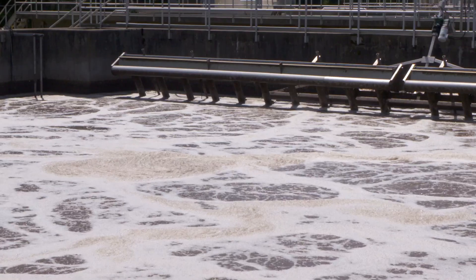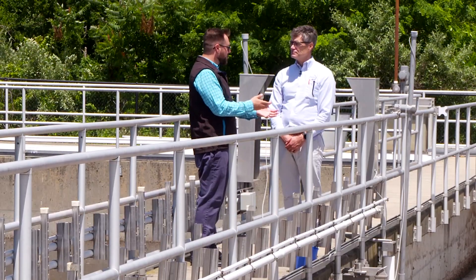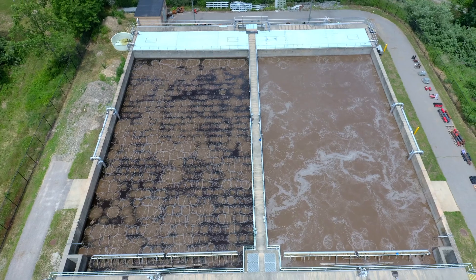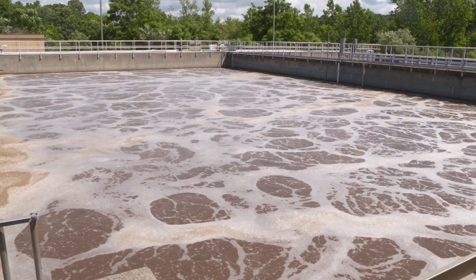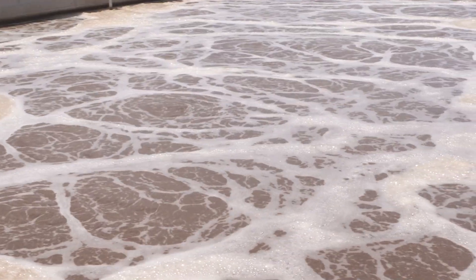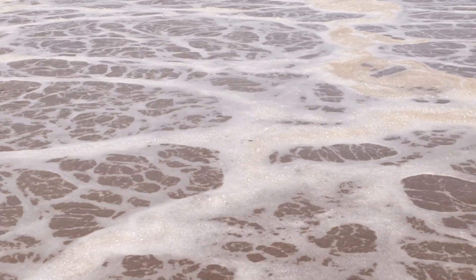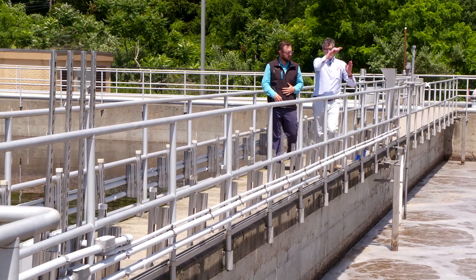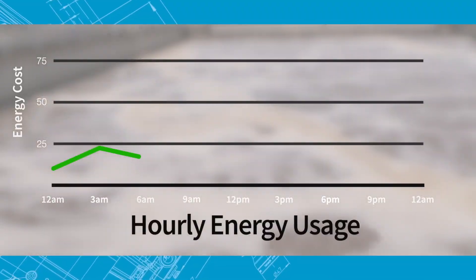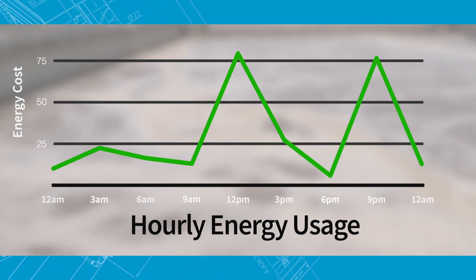You're wasting money because you're just pumping air right through the tank. You may be getting the same CFM or SCFM into the tank but because the oxygen is not dissolving in the water it's not actually hitting the DO. So you're having to turn on another blower and use more energy to maintain the same DO with poor process control. When we had the old delivery system we would have a very inconsistent feedback on our graphing system from SCADA — we would just see these giant humps of over-the-top DO concentrations within the tank. And when you're seeing those big humps, those are big spikes in energy as well — big spikes in energy, just a waste of air.